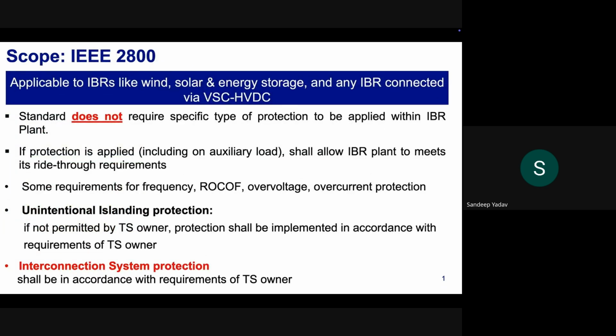So one of the recent resources for inverter-based resources is IEEE 2800, which defines various requirements of how the system should be connected to the bulk power system. How these generators, solar, wind, and other inverter-based resources shall be connected to the bulk power system. However, when it comes to protection, IEEE 2800 does not specify what kind of protection is to be used, and it is defined as per the requirements of the transmission system owner as to how the system should behave and what kind of protection is to be used. So anti-islanding protection, the kind of protection which is to be used at the point of interconnection, the responsibility still lies with the transmission system owner.